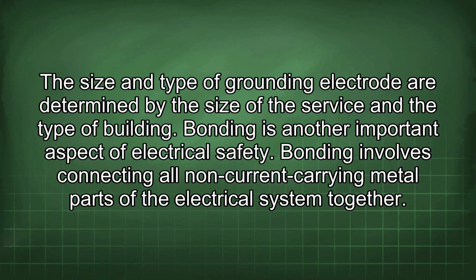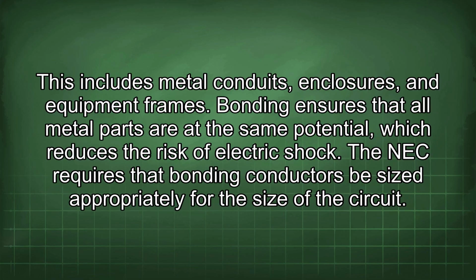Bonding is another important aspect of electrical safety. Bonding involves connecting all non-current carrying metal parts of the electrical system together. This includes metal conduits, enclosures, and equipment frames. Bonding ensures that all metal parts are at the same potential, which reduces the risk of electric shock. The NEC requires that bonding conductors be sized appropriately for the size of the circuit.